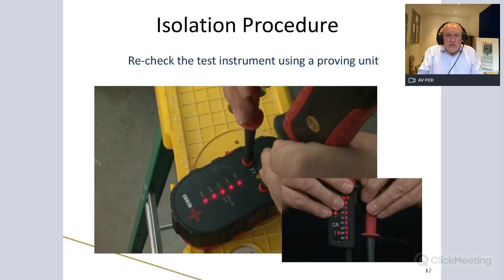So once we've actually checked it, we then retest the voltage indicator, because you never know - from when you initially tested it on the proving unit - whether something's changed. Let's say, for instance, you dropped it and it broke something inside. So when you tested it against what you thought was a dead supply, it could actually be a live supply.